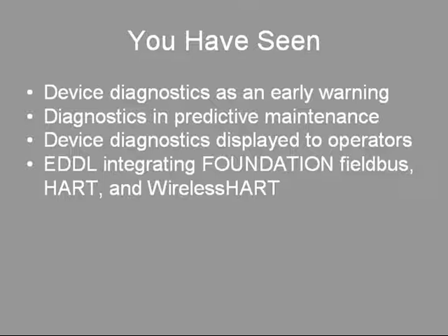Device alerts can be prioritized based on the criticality of the device to the process and the severity of the fault. Only critical alerts are annunciated on operator stations so as not to flood operators with alarms. All diagnostics is logged in the maintenance station. A technician at a maintenance console can see the same diagnostics and can also perform other device management functions such as device configuration and calibration. Integrated diagnostics is possible with EDDL because EDDL is not driver software, just compressed text. Other solutions use driver programs not permitted on control systems, therefore only displaying diagnostics on separate maintenance stations.